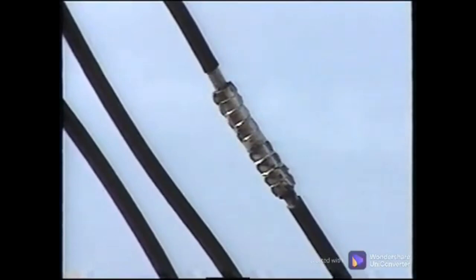There is usually some general concern for splices that are made in cables and should be checked for hot spots. The excessive heat generated by any loose connections can cause hot spots, overheat wires, which breaks down the insulation, and can cause other shorts in the system. When a loose connection is suspected, it is important to pinpoint the exact location. If the entire area is bright or hot, turn down the iris on the camera until only the hottest point is bright. This will be the exact source of the heat and most likely the location of the loose connection.